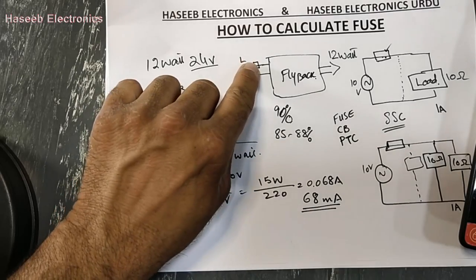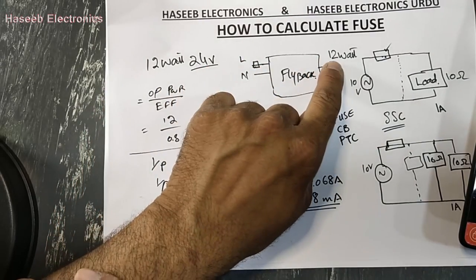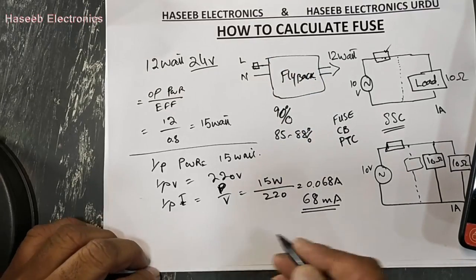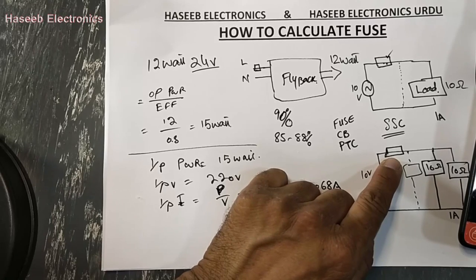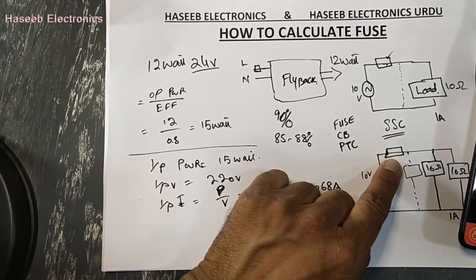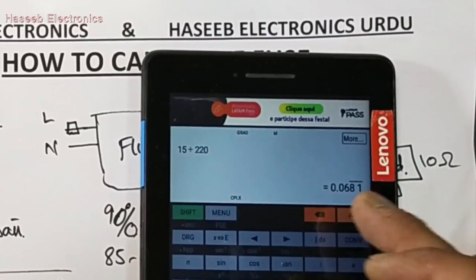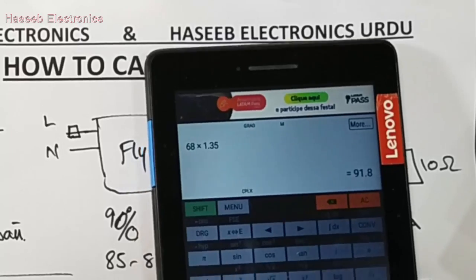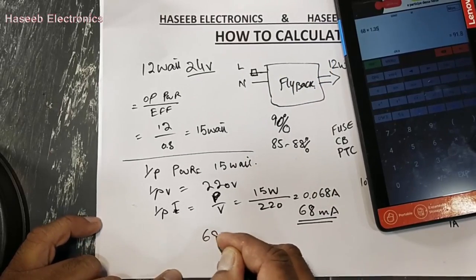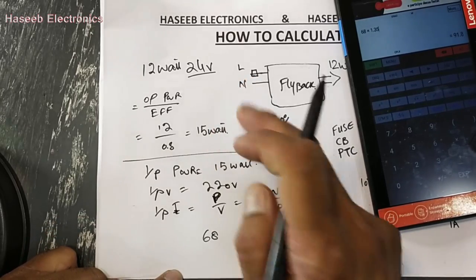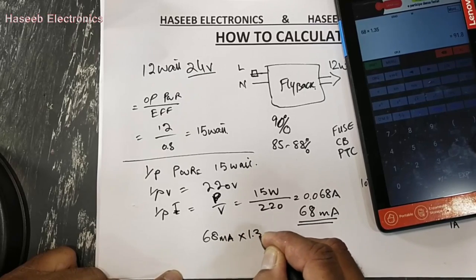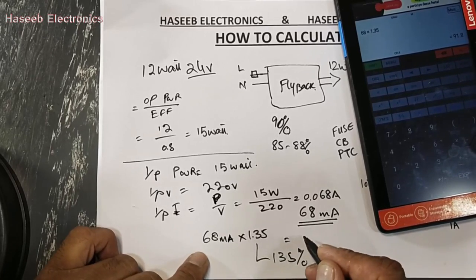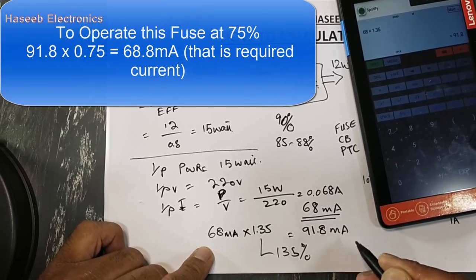Now when we select a fuse, the fuse will operate at about 75 percent of its total value. For easy calculation, take our 68 milliampere and multiply by 1.35 — that is 135 percent — giving 91.8 milliampere. This is the minimum fuse value we need to select.